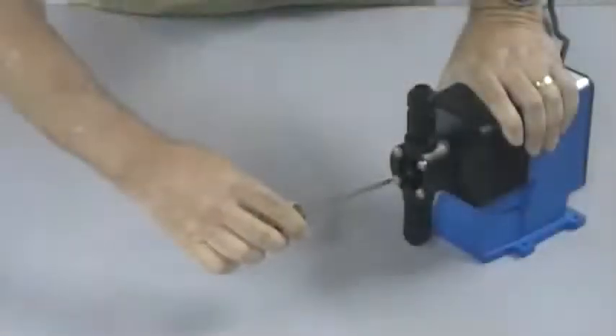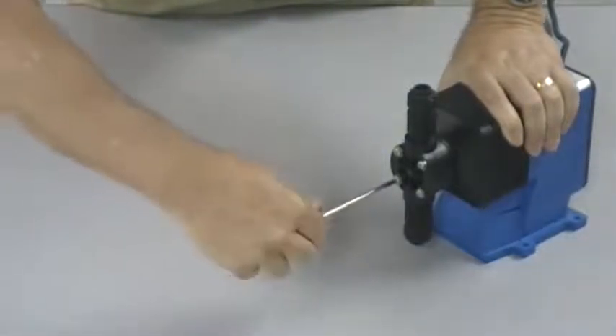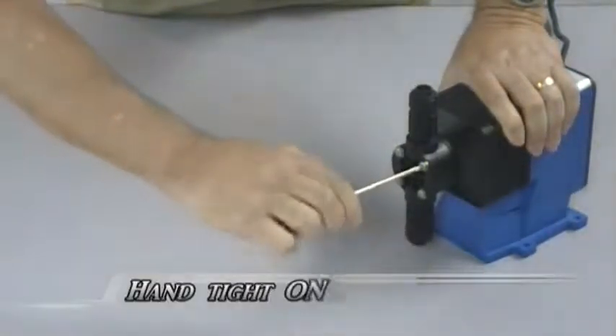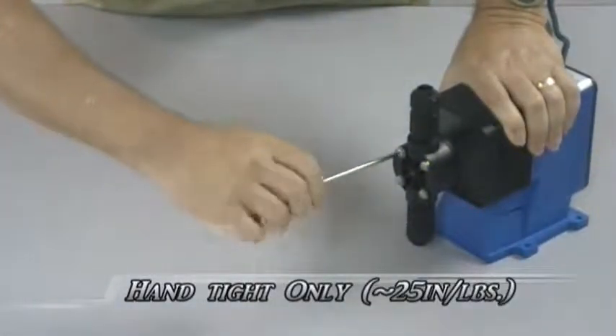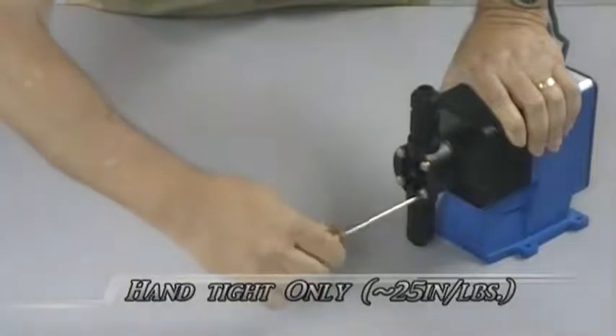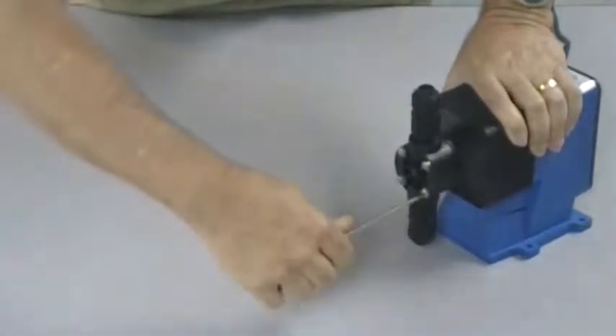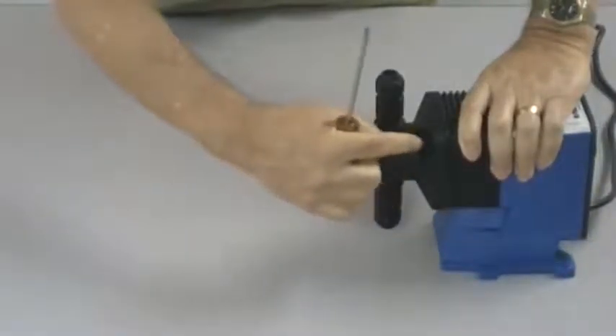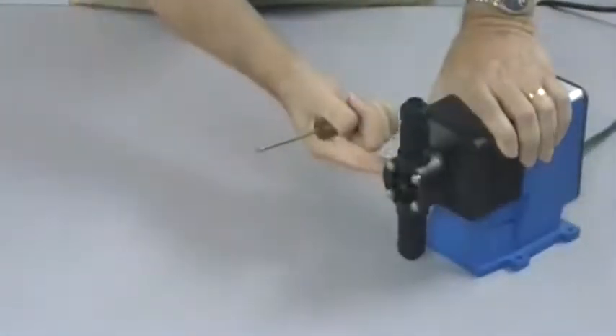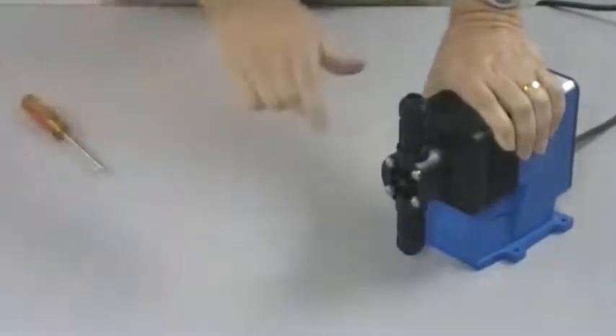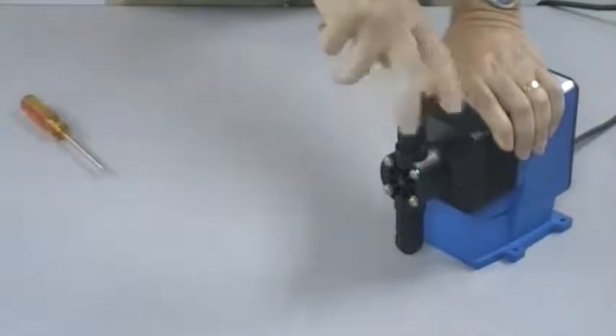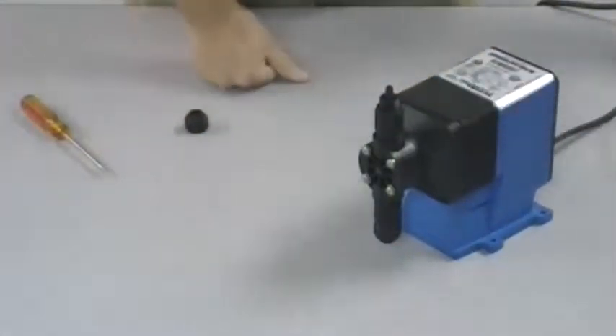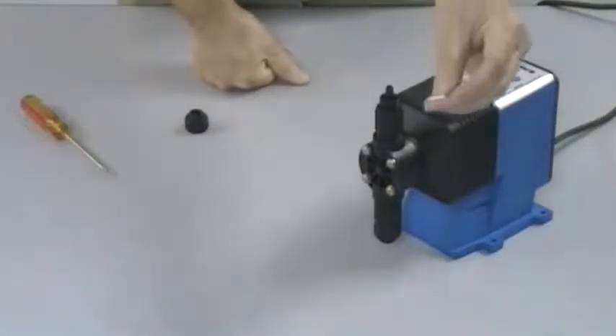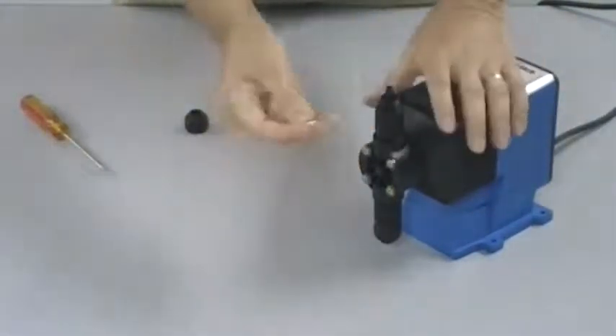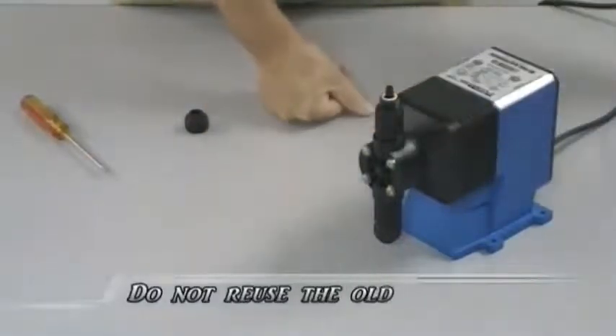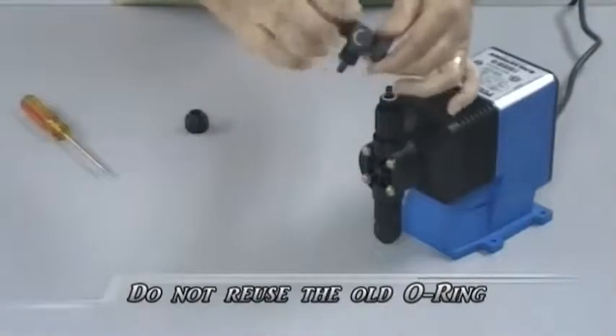Now we will finish tightening the head screws to the pump. This is done in a diagonal manner. We tighten them like this so that the gap here between the adapter plate and the pump head is even all the way around. Now we will remove the coupling nut from the discharge. Take our O-ring from our COP kit and place it on the discharge valve and reinstall the bleed valve from our pump.